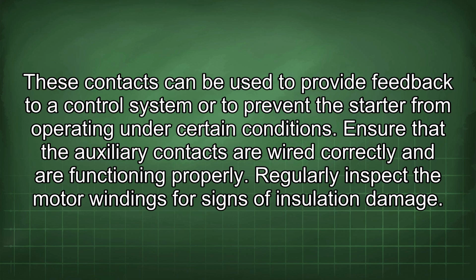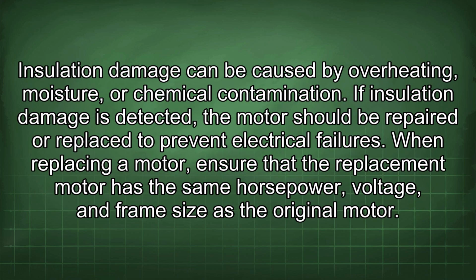Regularly inspect the motor windings for signs of insulation damage. Insulation damage can be caused by overheating, moisture, or chemical contamination. If insulation damage is detected, the motor should be repaired or replaced to prevent electrical failures.